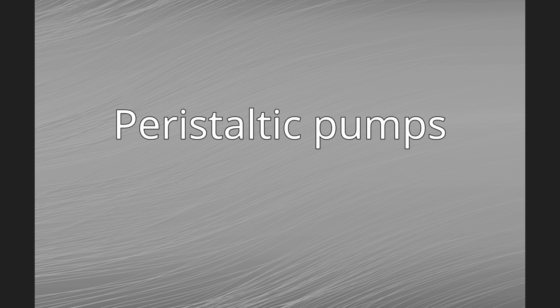Tygon R-1000 ultra soft tubing is used in general laboratory applications. It is the softest of the Tygon formulations with a durometer hardness of Shore 40, ASTM method D2240-2. Because of the low durometer of this material, it is often used in low-torque peristaltic pumps. Tygon LFL long flex life pump tubing, Tygon 3350, Tygon 50 HL medical/surgical tubing, Tygon 2275 high purity tubing, and Tygon 2001 tubing are also used in peristaltic pump applications.